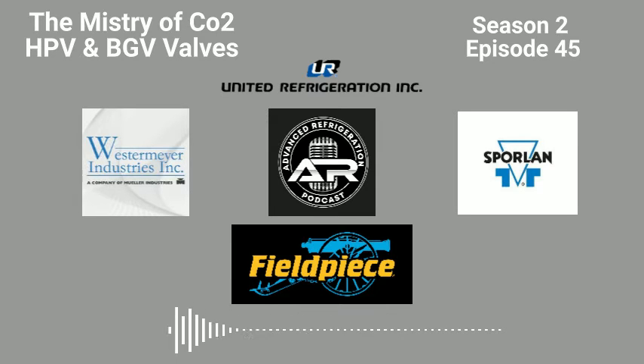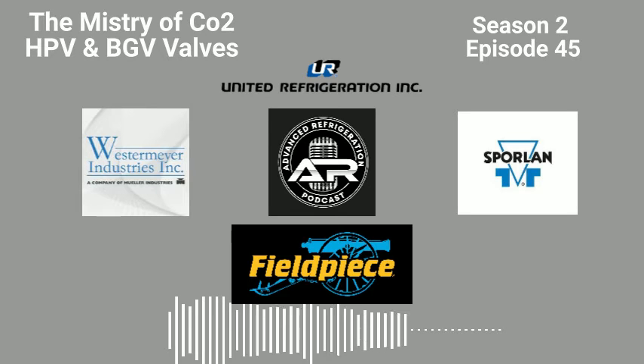because these racks, if you do not purge stainless while you're TIG welding, you get what's called sugar dust inside the pipes. So it's like crystallization from the rod and the actual stainless process. So it's like way finer, nastier than like braze dust. So like if you're brazing without nitrogen, and let's be honest, some of these tanks that are in these are just like filthy dirty. So, I mean, you don't really know what you're getting.